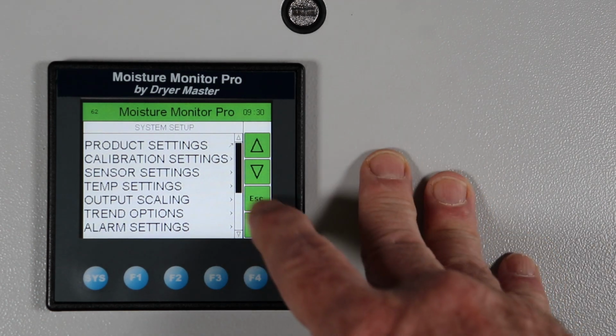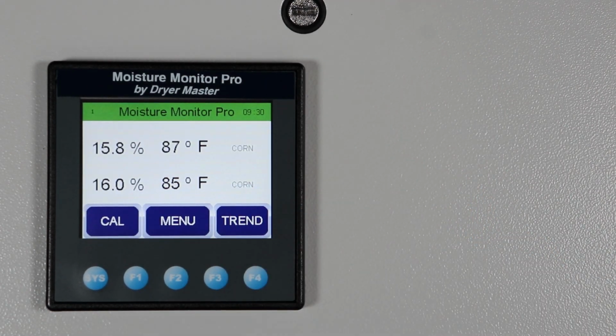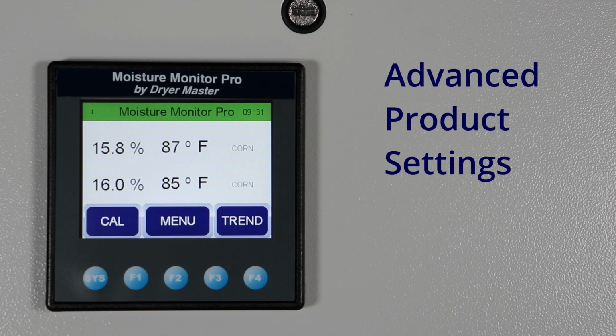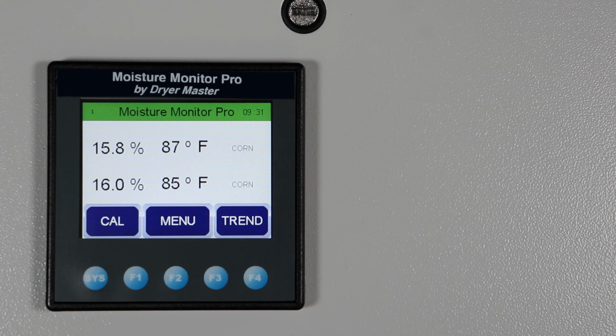Okay, there's one last thing I want to talk about, and that's, I said before at the very beginning that each product is set up a little bit differently. And it's kind of important to understand how each product, the settings for each product are important. So there's a couple of key parameters that we set up. And it has to do with basically how the sensor reads moisture. Different products of different densities require different parameters. What does that mean? It means basically we're getting a voltage back from the sensor. And if a product is very low density, we have to use a bigger multiplier on that voltage. So something like oats or sunflower is lower density, so we're going to use a bigger multiplier. Something like corn or wheat, which are heavier, would use a lower multiplier.